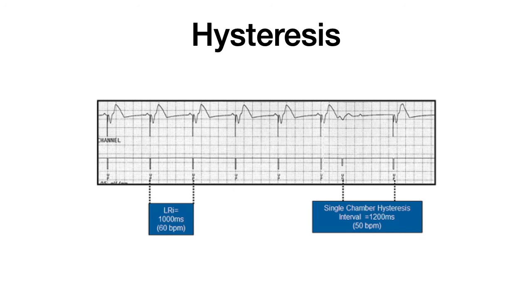When we come to the hysteresis function of the pacemaker, hysteresis is known as a common phenomenon in physical systems and occurs when the system's output depends not only on its present input but also on the past inputs. So a pacemaker, which usually allows a longer escape interval after a sensed event, will give the heart a greater opportunity to beat on its own. Let me explain it further.